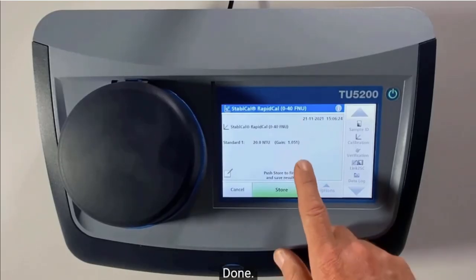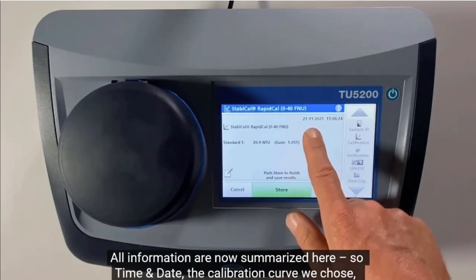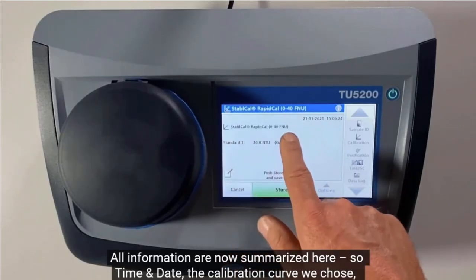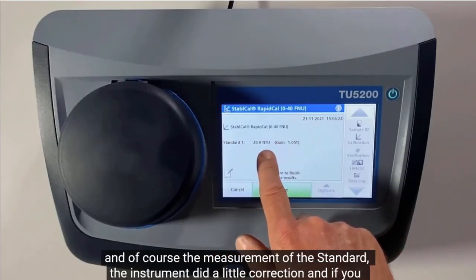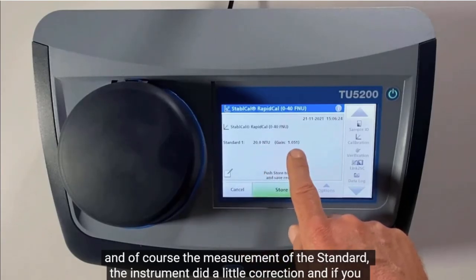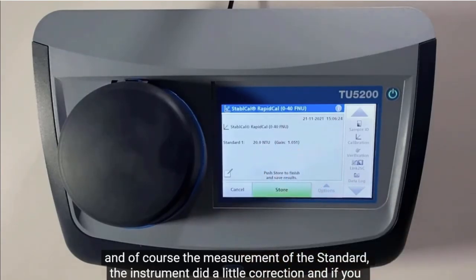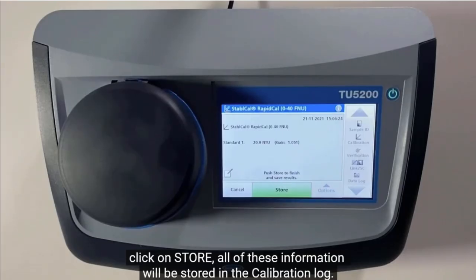Okay, done. So all information is now summarized here: time and date, the calibration curve we chose, and of course the measuring of the standard. The instrument did a little correction, and if you click on store, all of this information will be stored in the calibration log.